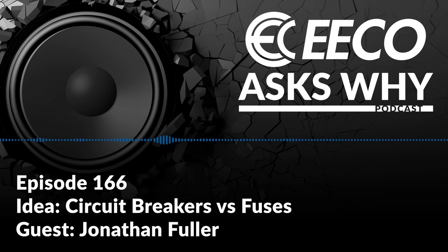Because if you have something that doesn't have the right characteristics for your circuit, just like a circuit breaker, it could cause something upstream to blow instead of the one that you typically want. And that could potentially be a safety issue. Absolutely. One best practice we haven't really talked about here: if you're going to replace a fuse, go back to the drawings and verify that the fuse you're pulling out was correct, first of all, and then that the fuse you're putting back is the same rating. Because oftentimes, we've all been there, things need to get up and running, and let me stick a penny in here and get up and running. Well, hopefully we're not doing pennies. Hey, I have seen them, though, those link-type fuses.